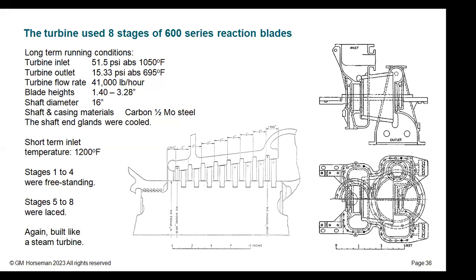Inlet conditions were about 51 psi absolute, 1050 Fahrenheit for most of the time, but 1200 Fahrenheit for short periods. Shaft diameter 16-inch, and it was made of only carbon half moly material. Carbon half moly was introduced about 1930 for steam turbines when temperatures went from 700 Fahrenheit, which only required carbon steel, to 800 Fahrenheit. And when we built 60 megawatt units in the 1940s, steam turbines, carbon half moly was suitable for 900 Fahrenheit. For 1,000 Fahrenheit steam turbines, we went to one chromoly-vanadium, a completely different class of material.